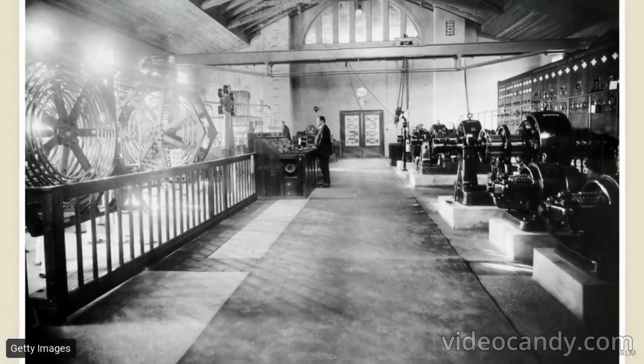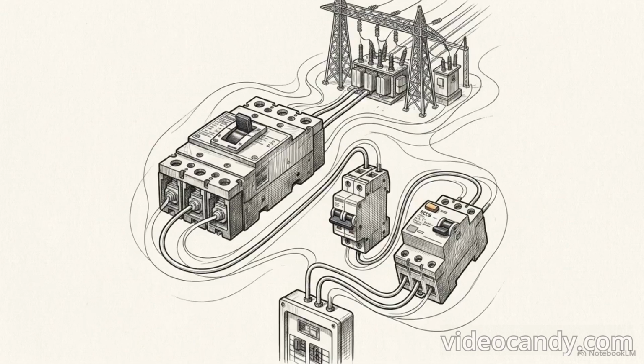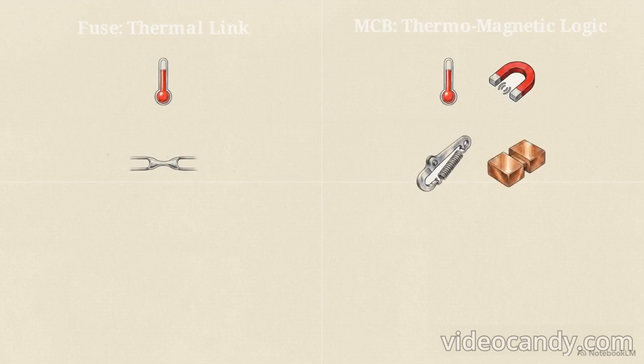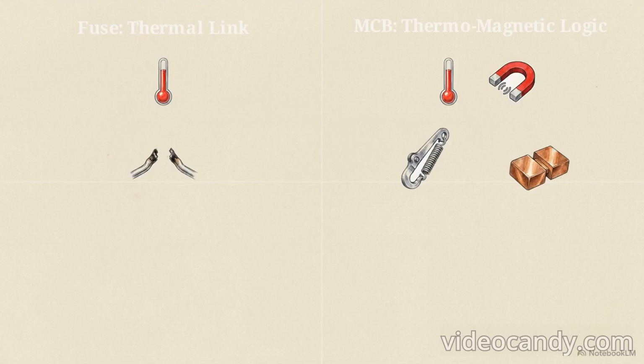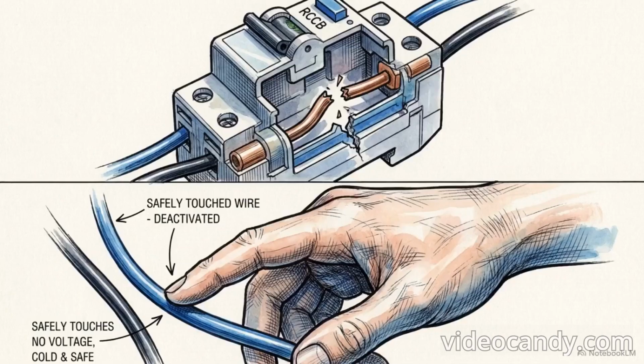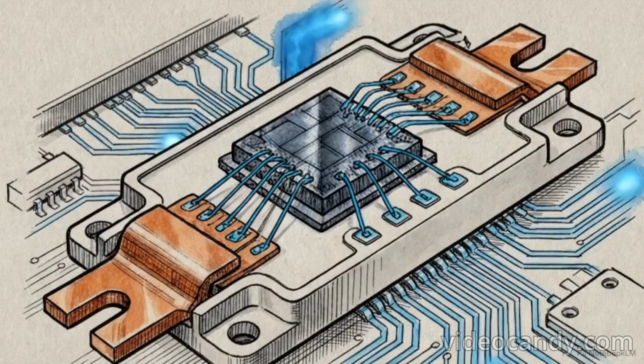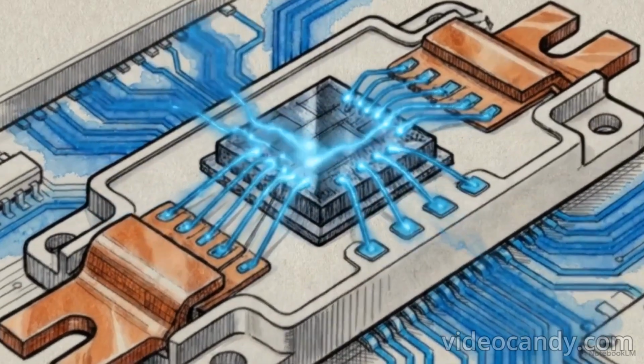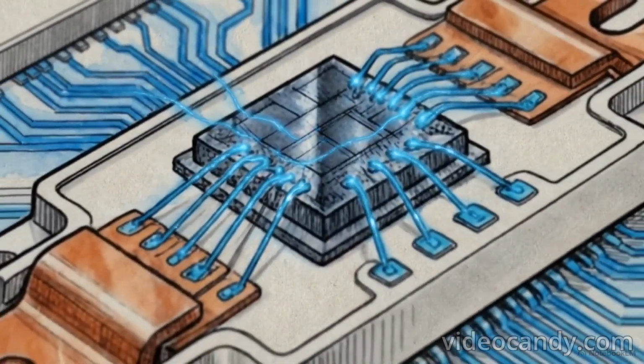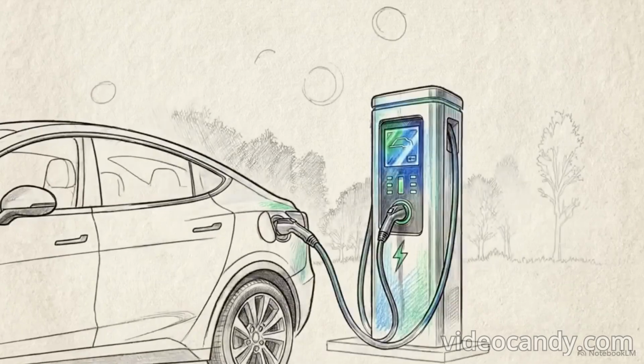The modern electrical grid is not protected by a single omnipotent device. Safety is achieved through a layered architecture, mapping specific hardware configurations to distinct physical threats. This matrix outlines how that hardware is deployed. We use sacrificial fuses and thermomagnetic MCBs as the primary bulkheads against infrastructure damage, manipulating heat and magnetism to stop wire degradation and short circuits. We overlay that system with differential RCCBs, relying on continuous Kirchhoff balances to intercept the tiny leakages that cause biological harm. And at the absolute peak of modern power demands, we substitute mechanics with solid-state silicon logic, eliminating physical degradation and arc flashes entirely. The grid is evolving.